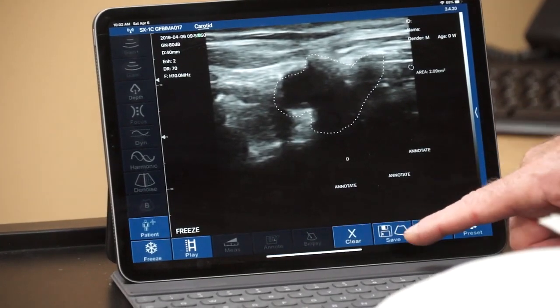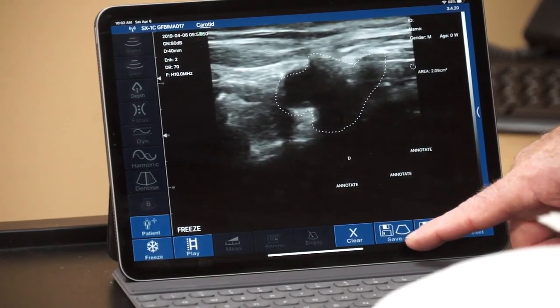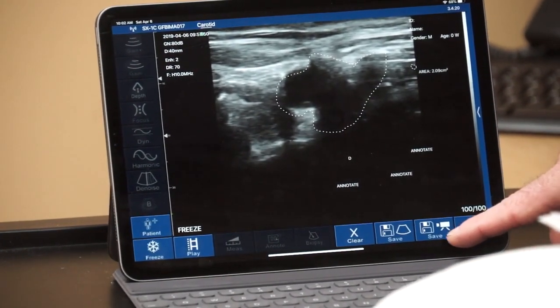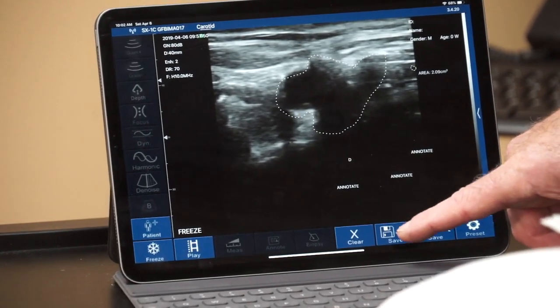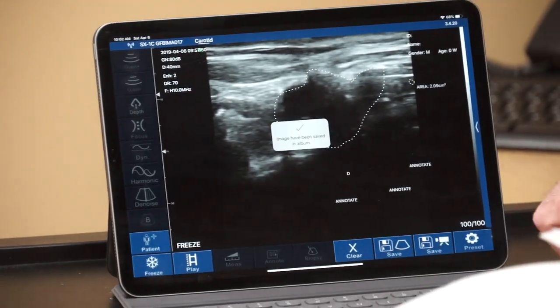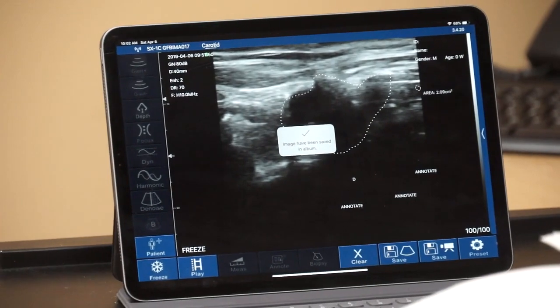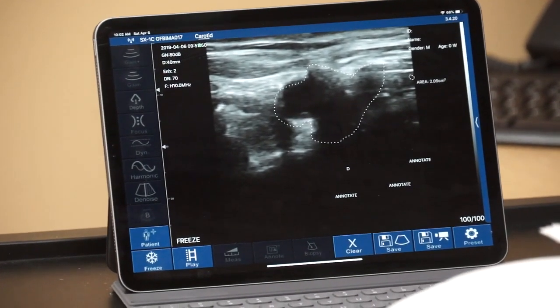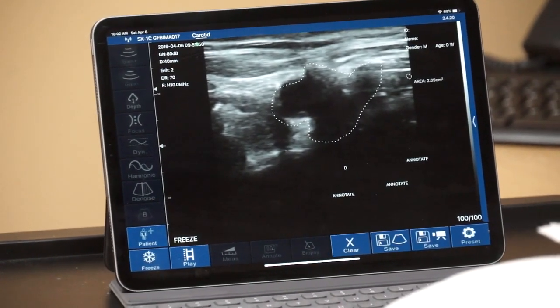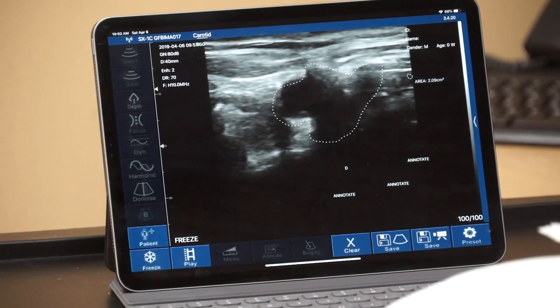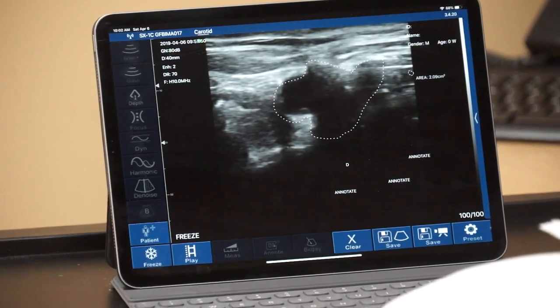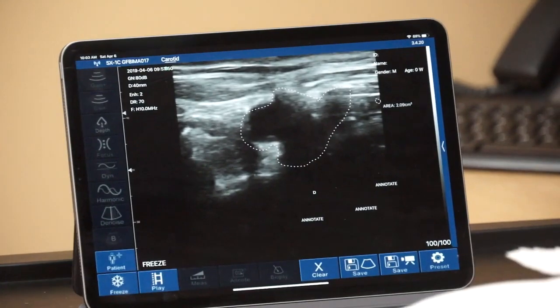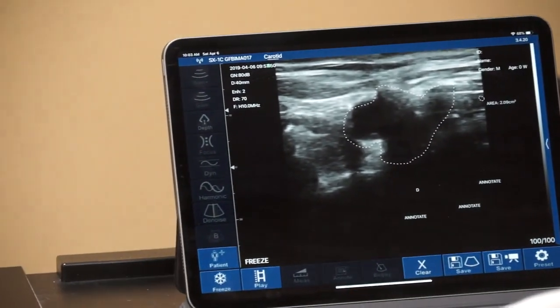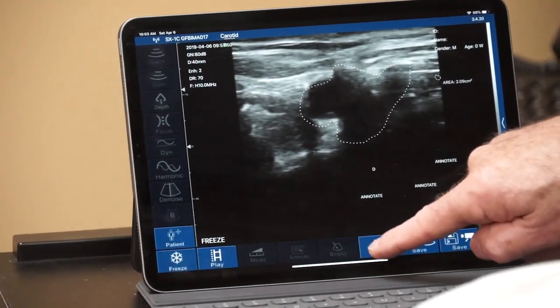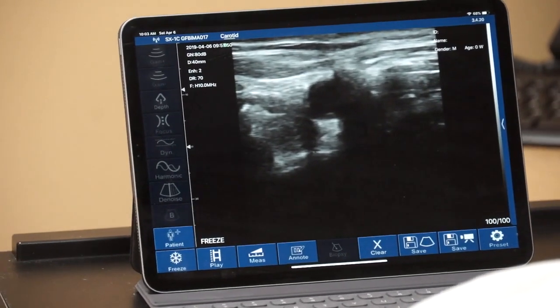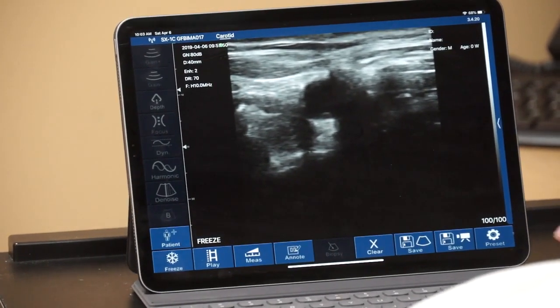At this point, I'm now ready to save the image in a single frame, or I can save the cine loop on the viewing device. If I hit the word save, I get a message that I was successful with my save, and now that's stored on the viewing device as a digital file. The individual images are stored as DICOM files, and the cine loops are saved as a .mov file or movie file. I'm going to clear that off, I'm going to restore the other options on the frozen image.